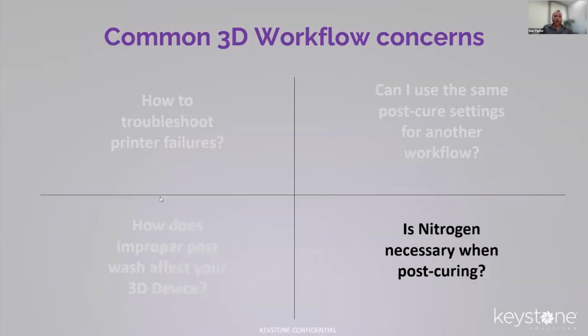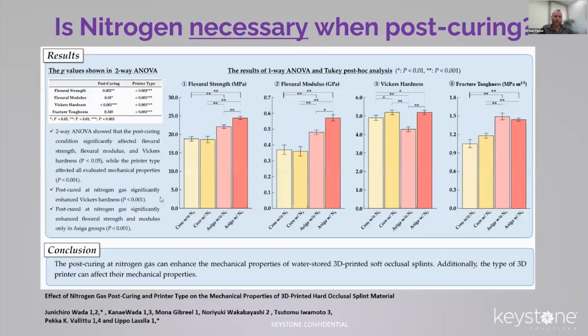And then our last question here is, is nitrogen necessary when post-curing? This is something that we get asked a lot. One of the biggest takeaways from this slide is that we always recommend it. Anytime you're printing and post-curing with a medical device resin, we would always recommend using nitrogen or using vacuum. There are different curing units that provide a vacuum aspect, which is doing the same thing. It's removing the oxygen from the environment to inhibit oxygen and get a better cure on the surface. So nitrogen isn't necessary, but it's recommended because, as you can see from these results with Keystone Soft across 2 different printers that were validated, the use of nitrogen does help increase mechanical properties and help surface quality. So that's why it's highly recommended.